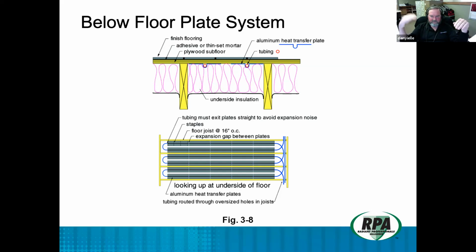If they don't want to use electricity, then the alternative is to set a boiler and a reverse indirect for domestic hot water, which then gives you the ability to pick up where the ground source heat pump leaves off. So if you decided that you needed 140 degree Fahrenheit water based on this application, then the ground source heat pump is good up to 115. And then from 115 up to 140, the ground source drops out and the boiler turns on and takes over for it. So it also provides you with copious amounts of domestic hot water for those teens that feel there is no end to hot water.